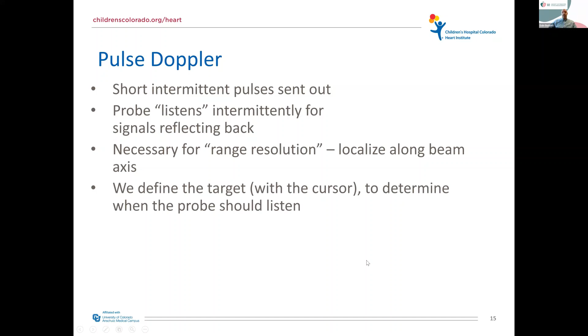So this is where it's going to be a little bit more confusing, but I think this is helpful to understand some of the other properties of Doppler. The time between pulses is known as the PRP, the pulse repetition period. And it's made up of 2 parts. The pulse duration, which is the pulses that are being sent out by the probe. And then there's dead time. And the dead time is because the signal has to go through the tissue to the target, hit that target and reflect back, and then the ultrasound probe is going to, again, code that as an image or velocity.